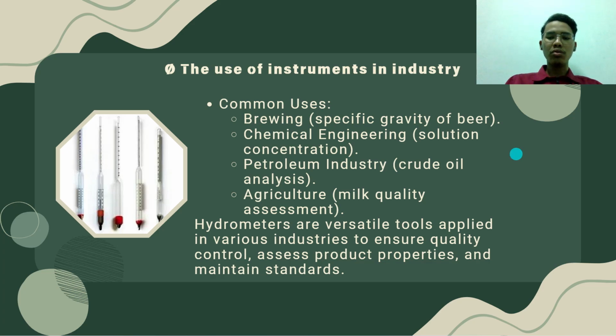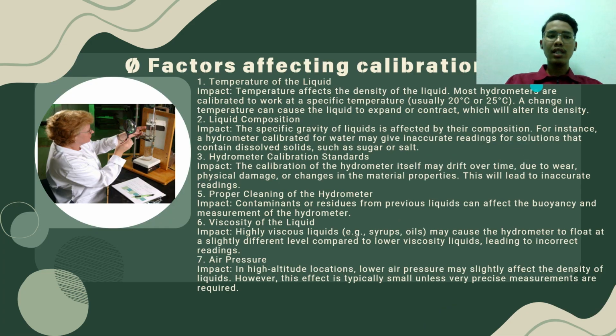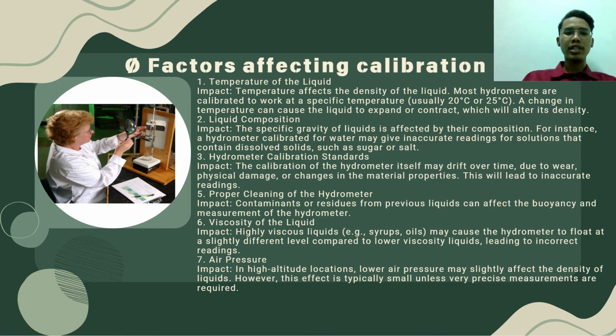The next slide is factors affecting the calibration. The first one is the temperature of the liquid, which impacts the density of the liquid. Most hydrometers are calibrated to work at a specific temperature, usually 20 Celsius or 25 Celsius. A change in temperature can cause the liquid to expand or contract, which will alter its density. Secondly is liquid composition. The specific gravity of a liquid is affected by its composition. For instance, a hydrometer calibrated for water may give inaccurate readings for solutions that contain dissolved solids, such as sugar or salt.